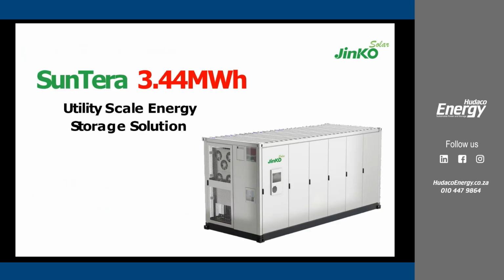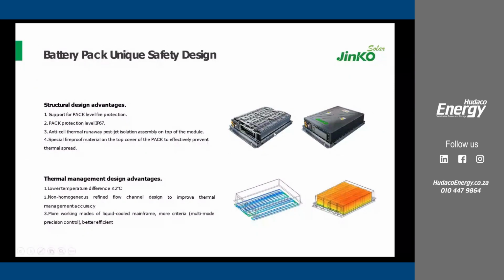Also, for the Sunterra and Sun Giga, the advantage is that with the cooling plates we've implemented, we've added what we call mica sheets. Mica sheets will avoid thermal runaway spreading from one pack to the next - if there's a fault in one of the packs, it will avoid the thermal runaway transferring to the next pack.